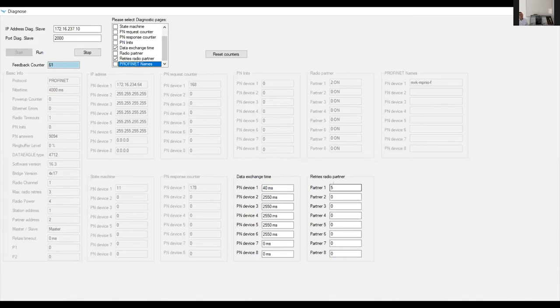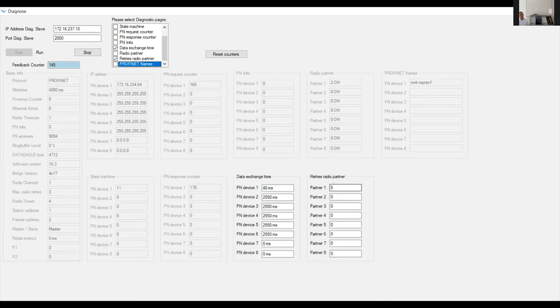When retries are counting up faster than before, it's an indication that something changed and you should check the system. You can act before there's a complete interruption of the wireless link — this is one of the main functionalities and very important to integrate into your project. It gives you an indication of how well the system is working. Another point for good working wireless solutions are the antennas, so I'll hand over to my colleague Supra.